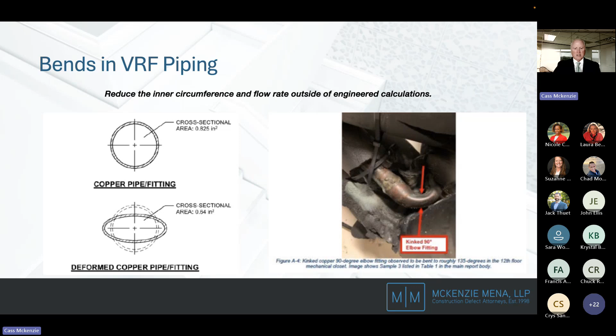In the summertime in Texas, that's detrimental, and it will start to affect the system itself. If you have bellies in the lines, this can affect the flow of the piping, and then you start getting compressor failure where the compressors burn out because the lubricant isn't properly getting back into them.